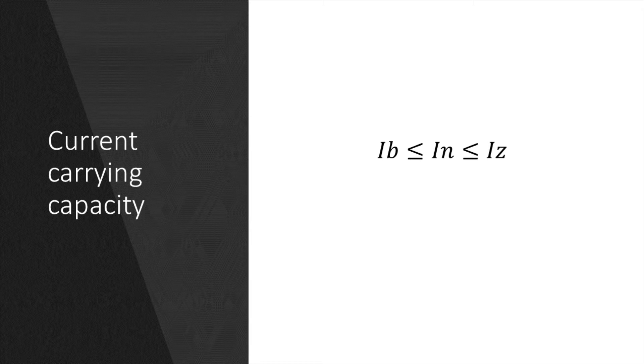The normal way of doing this is by making sure that the design current is less than or equal to the rating of the protective device, and then making sure that the protective device is rated less than or equal to the IZ of the cable. This can be expressed as shown here on the screen.